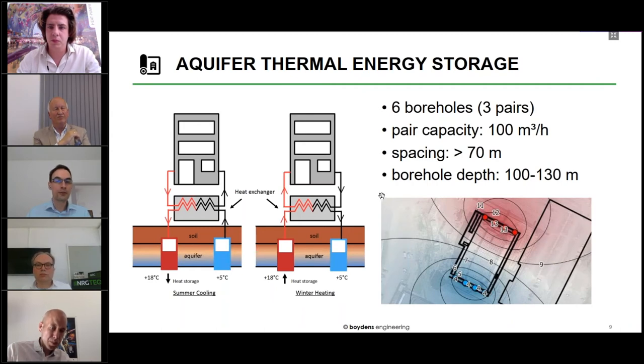So in fact, in total, we have six boreholes, but these are three pairs, and each pair is one borehole which is called a cold source, and another one that is called a hot source. So the total capacity of a pair is 100 cubic meters per hour. So in total, we have 300 cubic meters per hour of capacity, which amounts to more or less 4.5 megawatt peak capacity that is available. The spacing between the pairs is more than 70 meters, and the borehole depth is 100 to 130 meters.